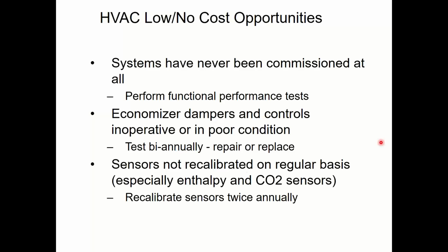But you may have systems older than that where they have old sensors, and you may need to be looking at those things. I normally recommend all these things be calibrated twice a year. Ideally, most buildings would have somebody doing maintenance on all the systems 4 times a year. I realize people aren't always going to pay to do it that way, but ideally, every packaged rooftop you have or whatever it is on your building, someone mechanically inclined would be visiting that thing 4 times a year, every 3 months, and making sure everything's working correctly. Now, maybe you're not always working on the same thing. When I go do my maintenance check in December, maybe I'm not bothering to check the cooling cycle, right? And when I do my check in June, maybe I'm not bothering to check the heating cycle, right? But I'm doing different things on each of those. And on 2 of those 4 events, the annual events, I'd like you to check the sensor calibration.